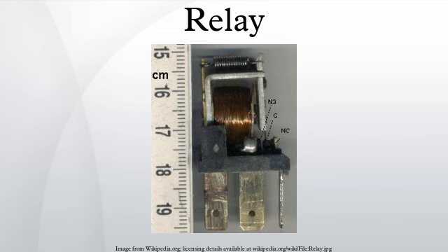There are many considerations involved in the correct selection of a control relay for a particular application. These considerations include factors such as speed of operation, sensitivity, and hysteresis. Although typical control relays operate in the 5 milliseconds to 20 milliseconds range, relays with switching speeds as fast as 100 µs are available. Reed relays, which are actuated by low currents and switch fast, are suitable for controlling small currents. As for any switch, the current through the relay contacts must not exceed a certain value to avoid damage.